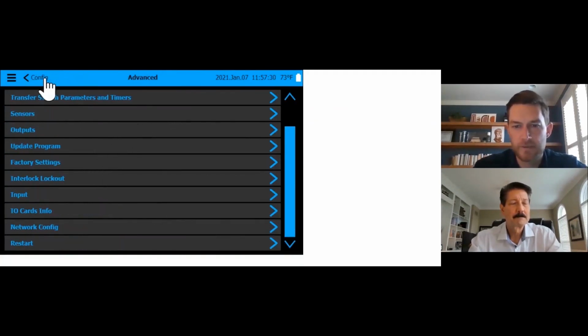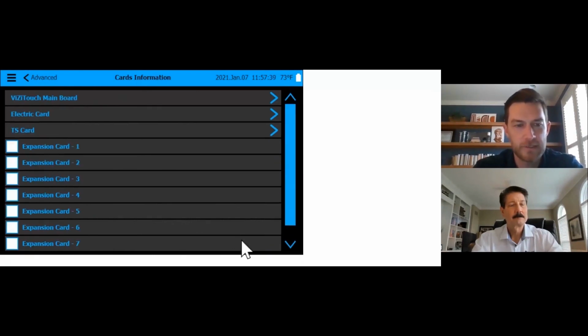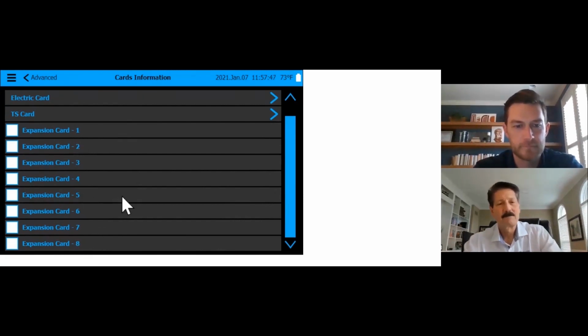There's also one thing to know. We're not limited to just those 6 alarms. If you want 25 alarms, we can do that. There's always expansion boards if somebody has needs for more alarms. Well, there you go, the expansion cards. 8 expansion cards, I think, what, 8 to 10 contacts per board? Yeah, we can add a lot. It's pretty easy. What we'll do is we'll install it. It's really a daisy chain from the existing IO board and a click on expansion 1 to turn it on. Right.